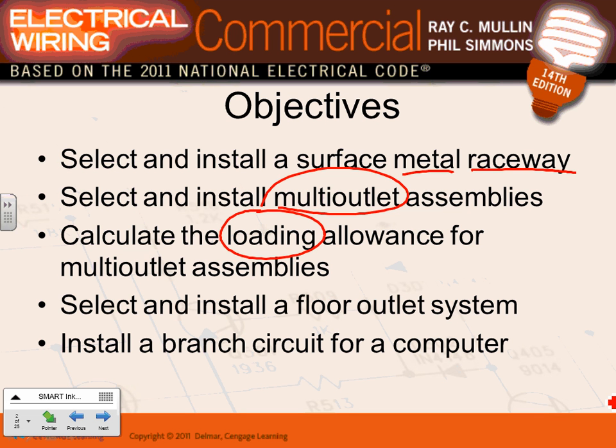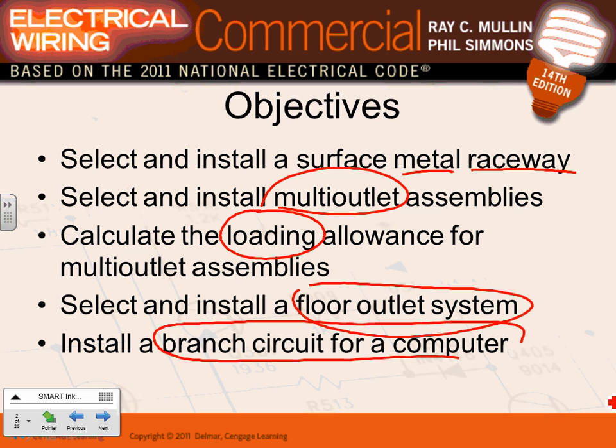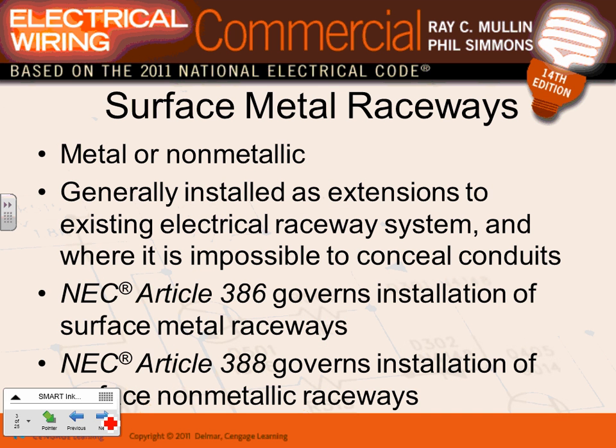For multi-outlet assembly loading: if it's simultaneously used, we give 180 volt-amps per foot; if it's non-simultaneously used, we give 180 volt-amps per five feet. We already know that loading. We'll also select and install floor outlets, under-floor raceways, and talk a bit about the branch circuit for a computer. That's the objective of this class. There's an article that talks about metallic or non-metallic raceways.